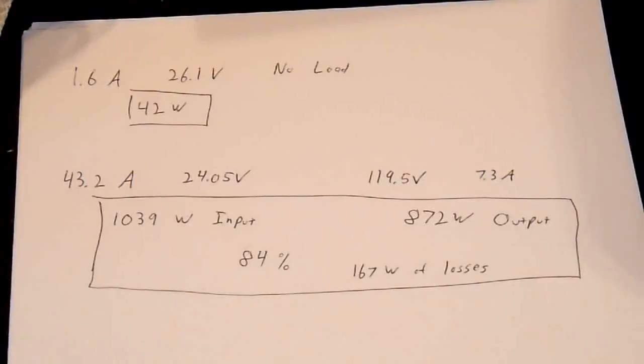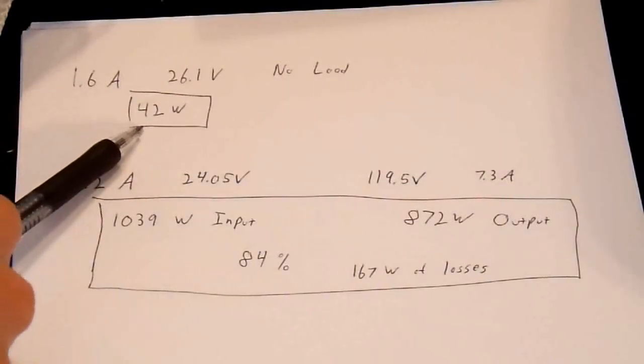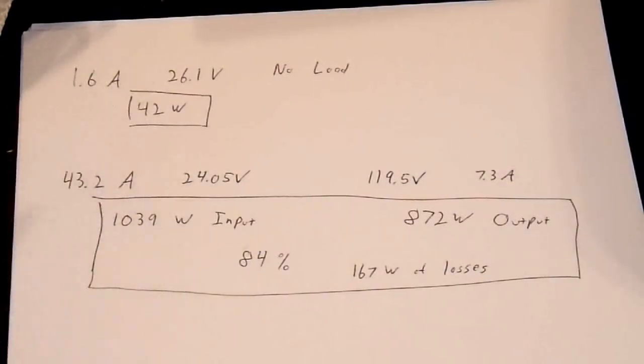After some very simple math, I have the results of this test. Under no load, it takes 1.6 amps out of the battery bank, with the battery bank at 26.1 volts, which yields 42 watts. That would be primarily dissipated in the transformer of the unit. The specification from American Power Conversion Company is 50 watts standby, so this matches up pretty well.